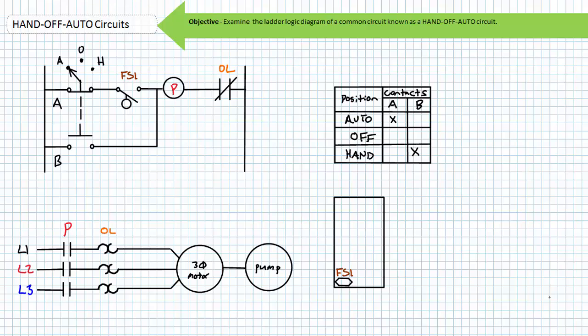The top rung of the ladder logic diagram contains the A contact of the selector switch, a normally open float switch, the P contactor coil, and the normally closed overload contacts.